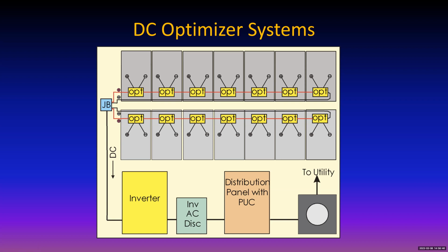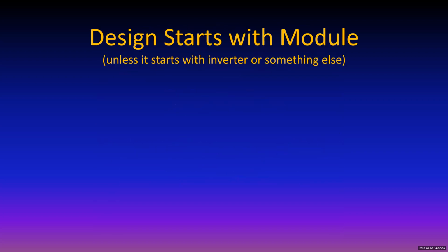And again, it's pretty much the same stuff down at ground level, except here's where your inverter is. The inverter is not on the roof under the module. It's now down below, and it has to be capable of handling the total power of the array. If it can't, well, you can always put more than one array up there, 2 of them, and use 2 inverters, or 3 or 4 or 5, and you combine the outputs of the inverters, run that into an AC disconnect. That feeds into the distribution panel. And sometimes that AC disconnect will simply be a backfed circuit breaker in the distribution panel. It depends on the size of the system and local ordinances and local rules, and utilities. Anything you don't use on site, you can sell back to the utility. So there's your optimizer system.